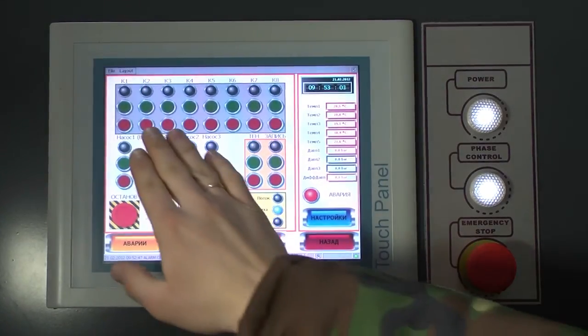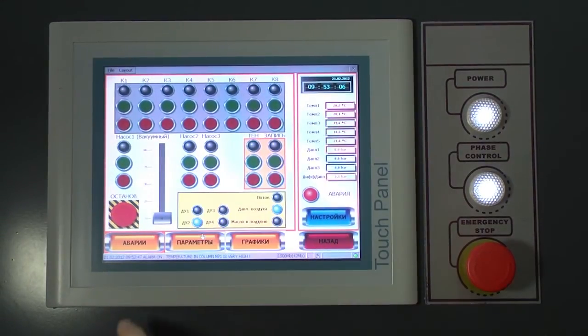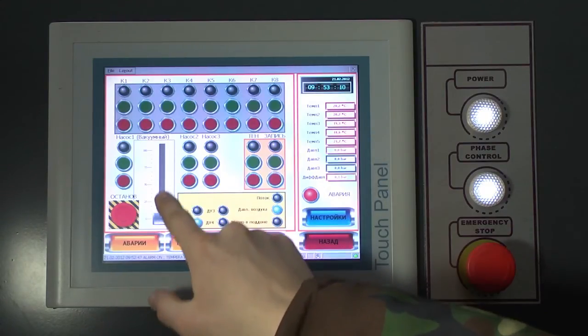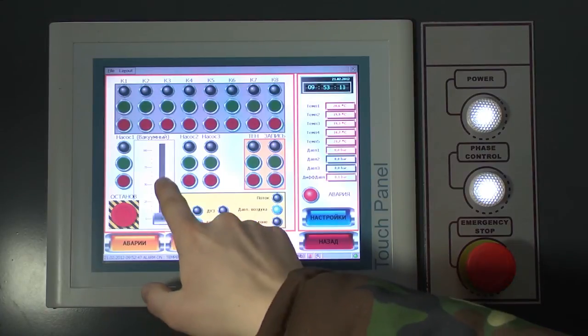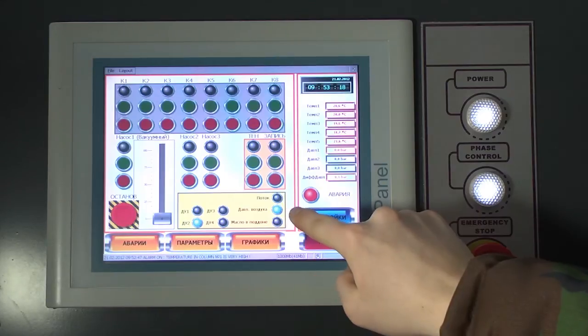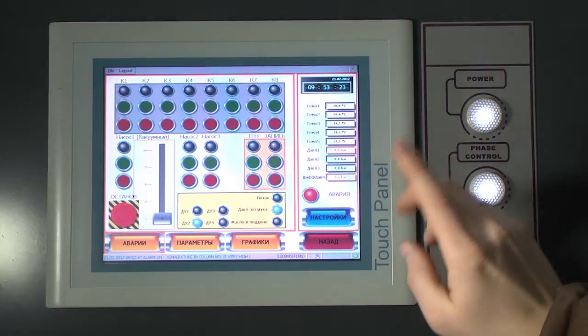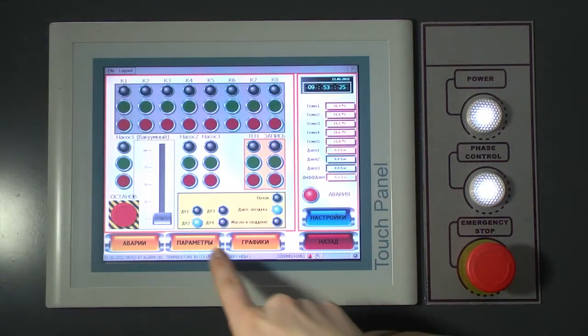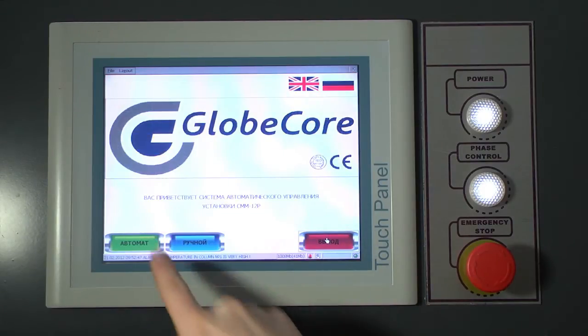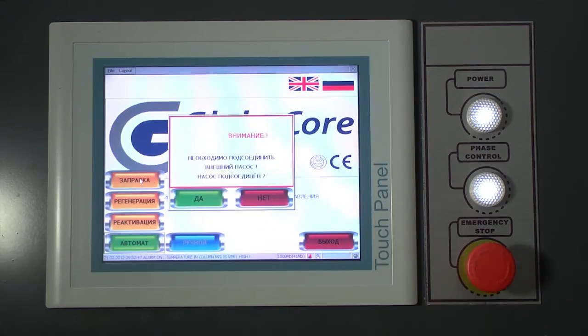It features manual and automatic operation modes. The manual mode makes all valves, pumps and the vacuum pump accessible for direct control. Pump rotation speed is controlled with a slider. The panel displays oil flow, air pressure, presence of oil in the base, emergency shutoff, graphs, parameters and malfunctions. Three modes of operation are available in the automatic mode: filling, regeneration and reactivation.